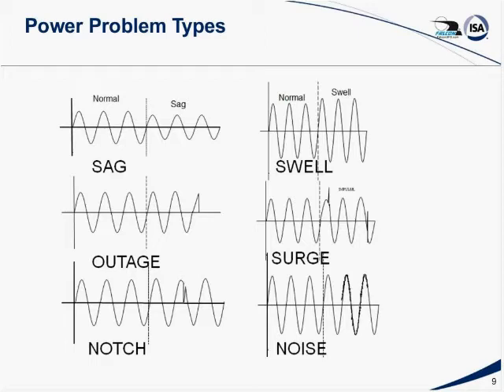These are generally up to 10%. And undervoltage would be a sustained low voltage, a sustained sag, greater than 1 minute. It's often called a brownout. A complete outage, where you lose power completely, can last from several cycles to however long it takes them to restore power, or you get your diesel back up and running. That's known as an outage.